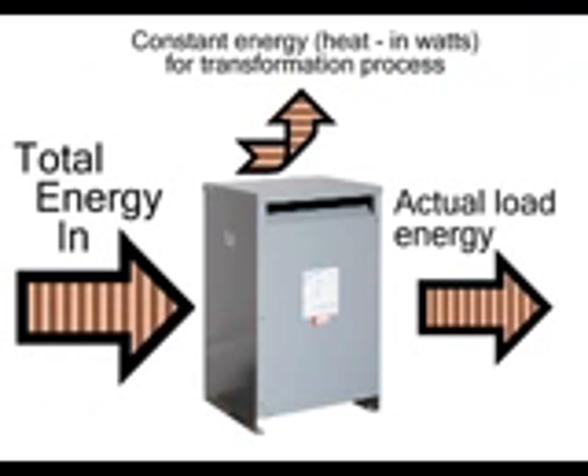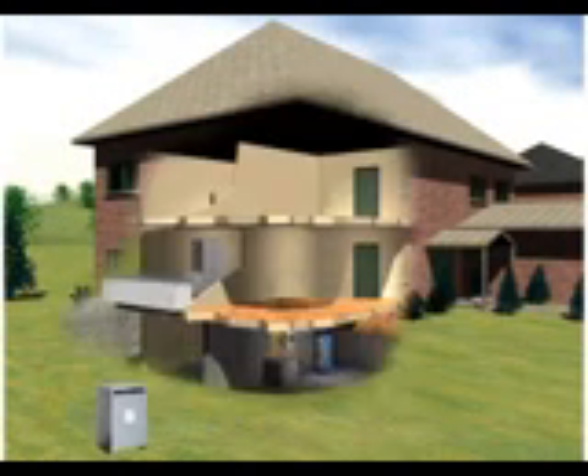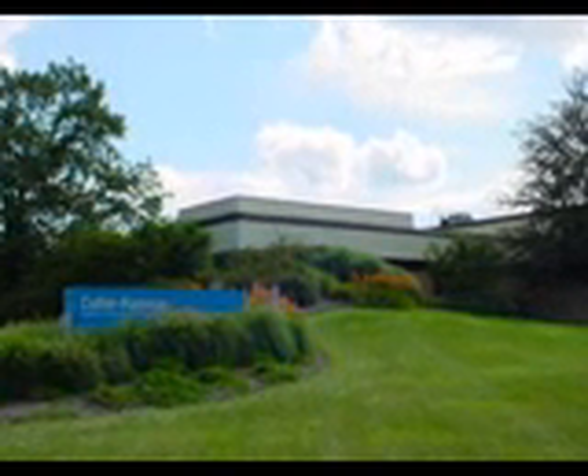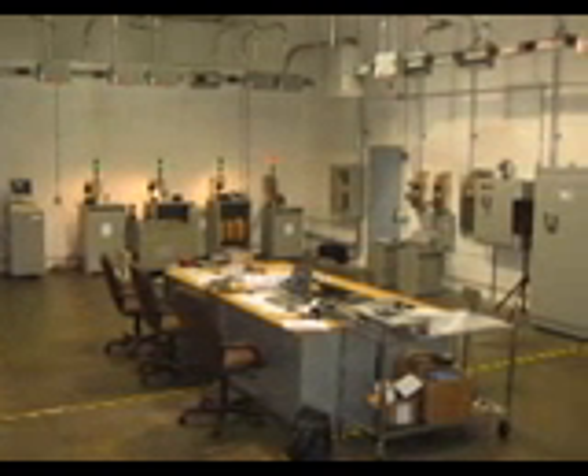Eaton has gone one step further to show customers the real-world performance of the HMT inside of their buildings. In the fall of 2006, Eaton conducted HMT transformer performance testing with linear and nonlinear load. This transformer testing occurred at the Eaton Power Quality Experience Lab in Warrendale, Pennsylvania. This lab is specially equipped to handle this type of testing because it has both linear and nonlinear load.